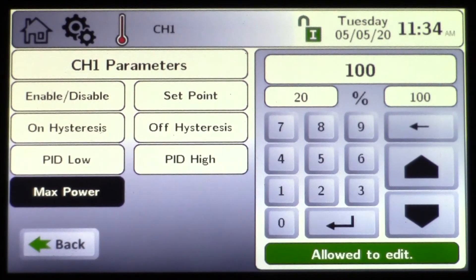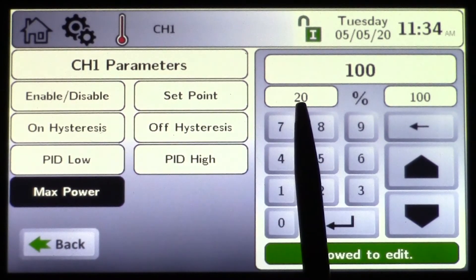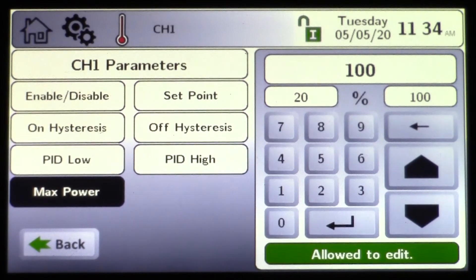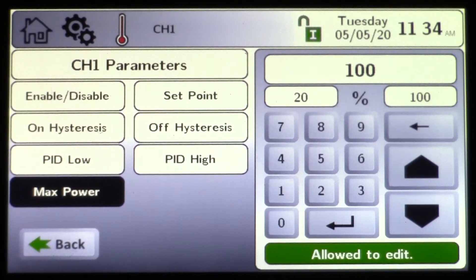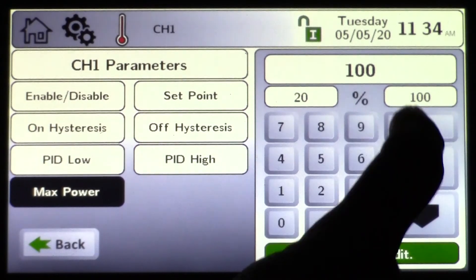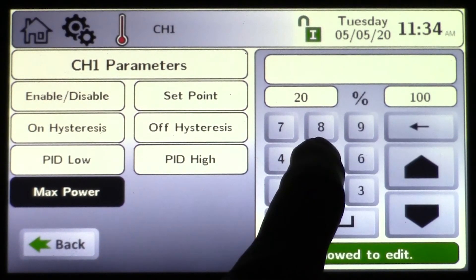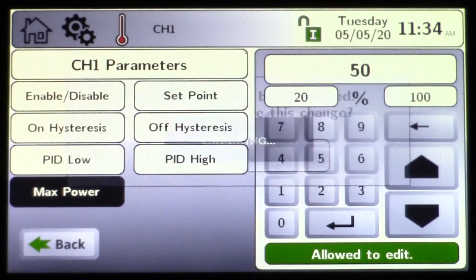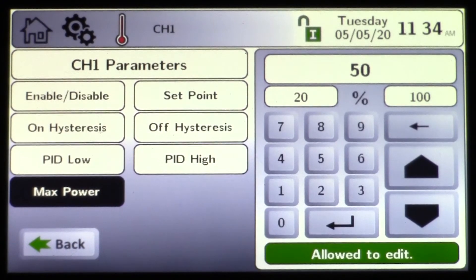Max power allows you to de-rate a boiler if needed, with a range from 20% to 100% of fire. For example, if a service technician is on a job where the gas regulator can't keep up — we need 4 to 10 inches of gas pressure and the boiler flames out or trips on a low gas pressure switch at high fire — you could back this out to 50% and operate the boiler at 50% until the gas company can correct the regulator.